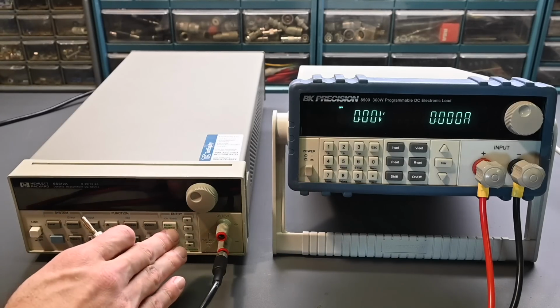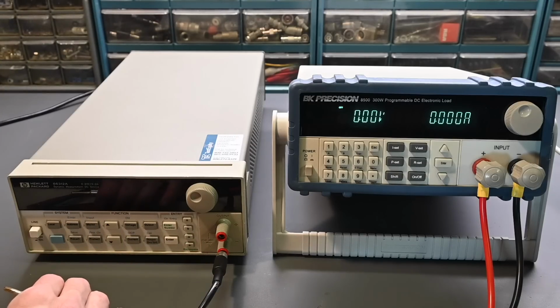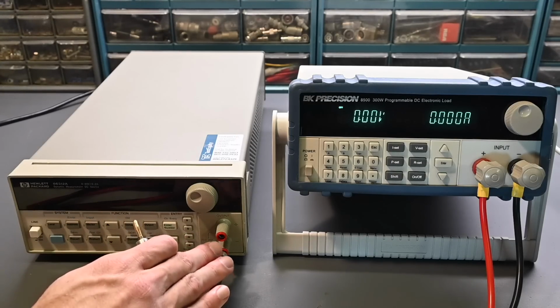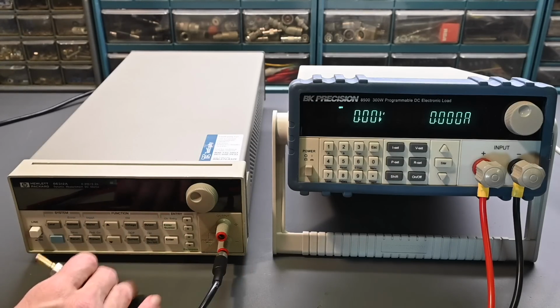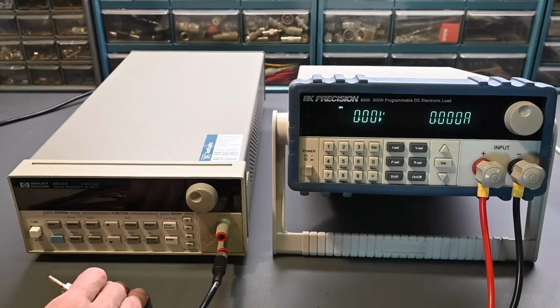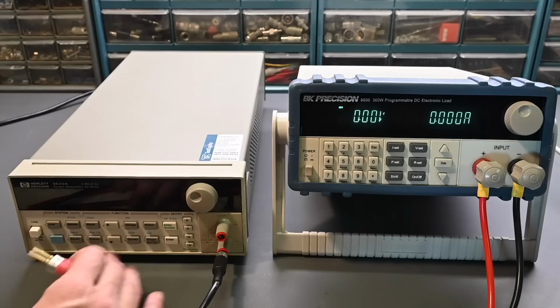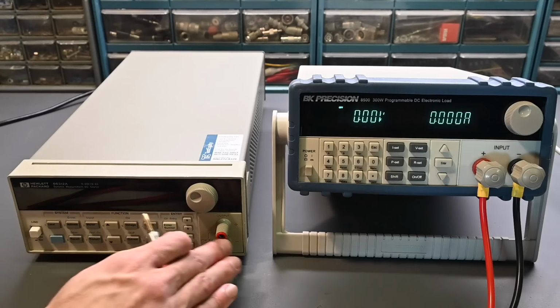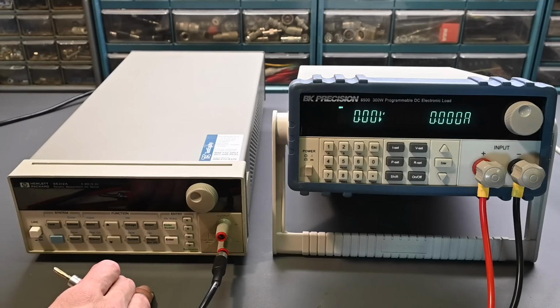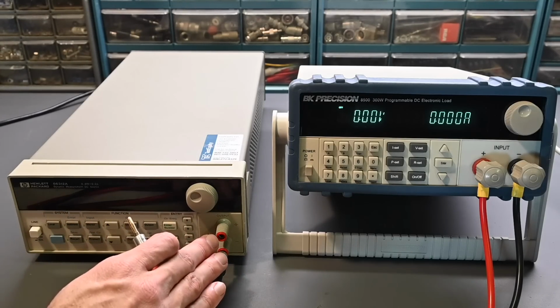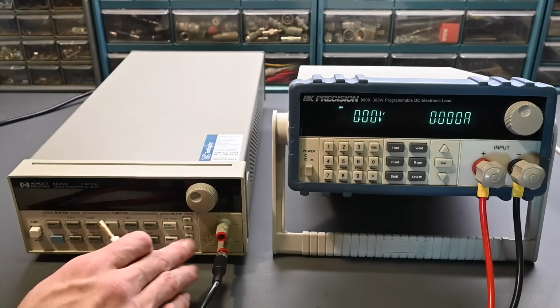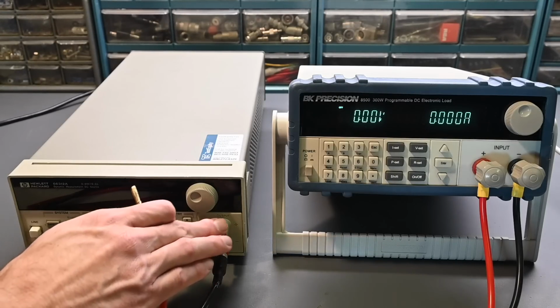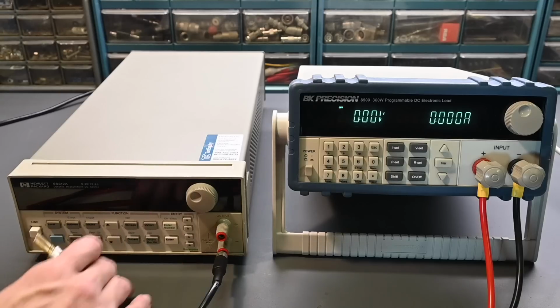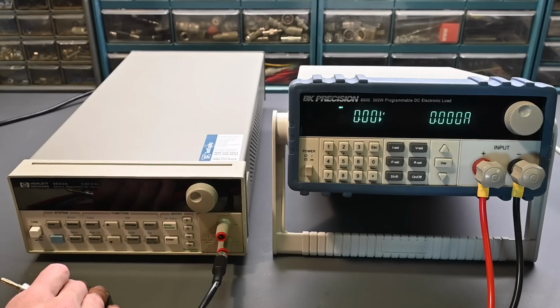Now this power supply can sink current as well as, of course, sourcing current, but sinking current means that the connected voltage is higher than the program voltage, and in that case current will flow back into the power supply. And internally there's a transistor, it's known as a down programming transistor, and it will conduct and basically just dissipate that current away as wasted heat into the heatsink. But when you're sinking current into the power supply, the polarity would still be positive on the top, negative on the bottom. You wouldn't flip the polarity, so I don't know exactly why they chose the red color for both of them.